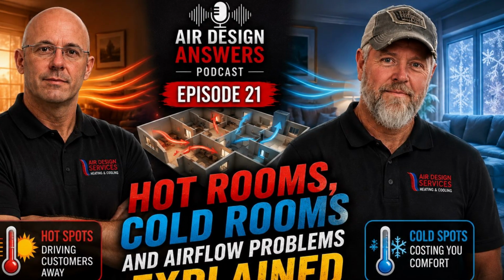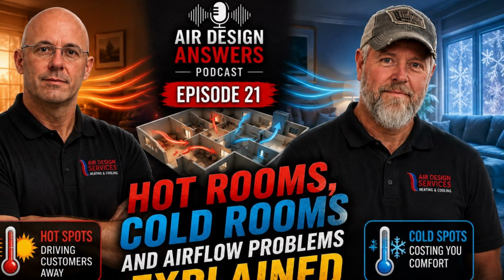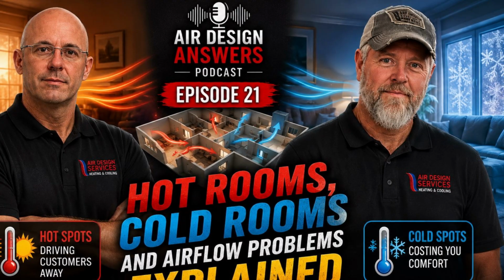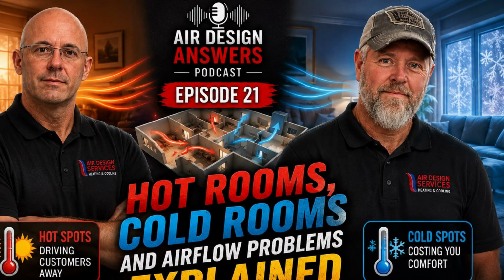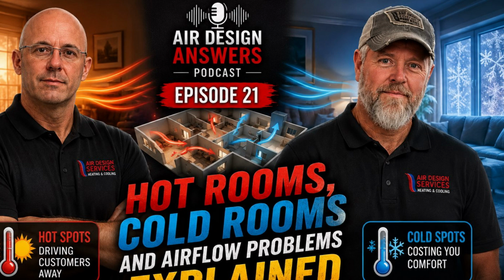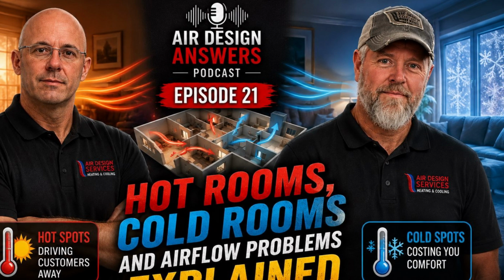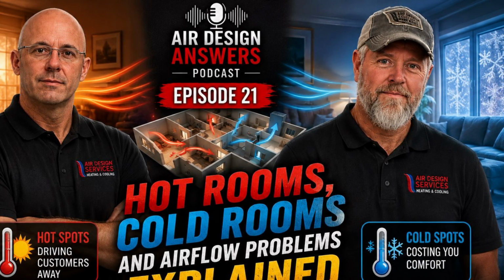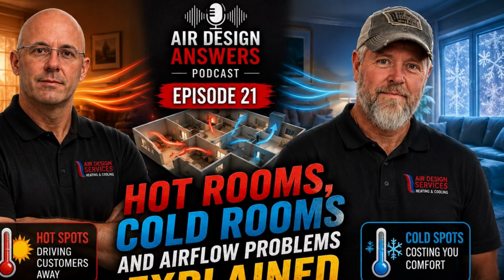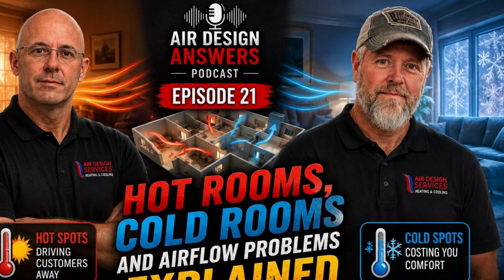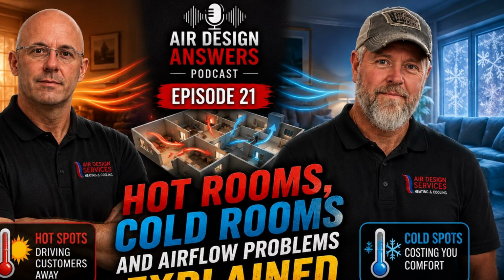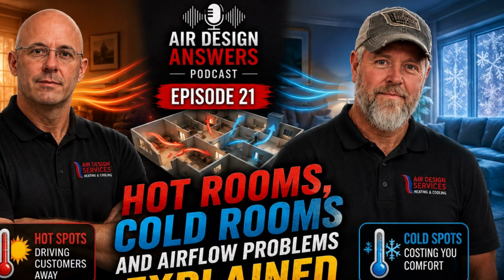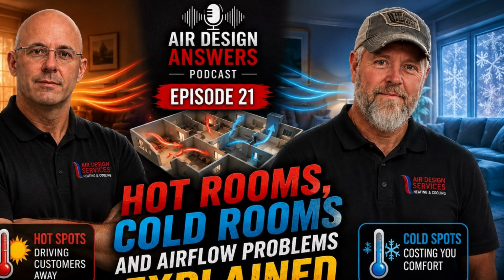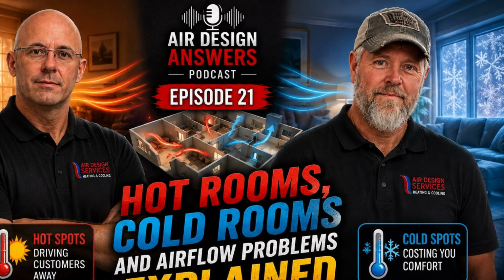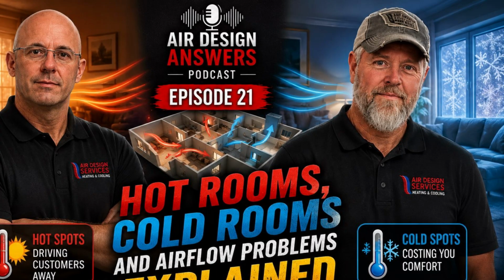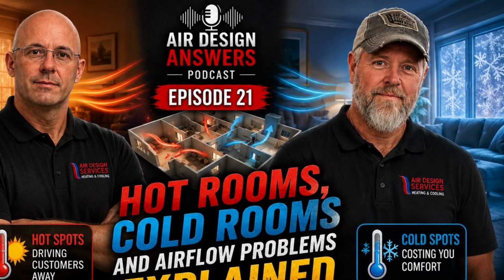One thing homeowners often ask is why airflow issues seem to get worse over time. They'll tell us the house felt okay when they moved in, but now certain rooms feel completely different. There can be several reasons for that. One of the most common is simply that homes change over time. People renovate, they finish basements, they add insulation, they replace windows, they build additions. The HVAC system was originally designed around a certain set of conditions, and sometimes the house evolves while the airflow system stays exactly the same.